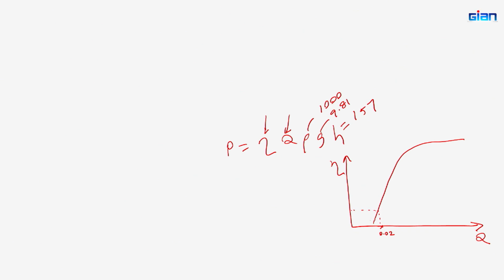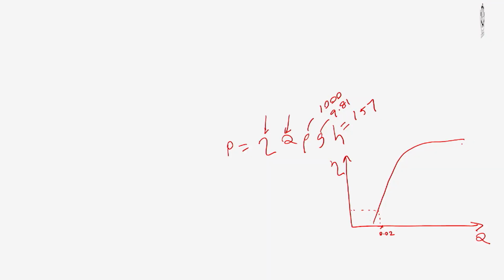One way is to fit a curve for this efficiency curve. How do we get the efficiency curve? We can get it from the turbine supplier. He will say this is the efficiency curve for my turbine. Once you know the efficiency curve, theoretically you can fit a curve on this. I am sure all the engineers are familiar with curve fitting techniques, using MATLAB or even simple hand calculations. You can fit a parabolic or some other curve suitable for this shape. Then you can just insert the flow value and calculate the efficiency. So, the efficiency will be an equation of flow. You can derive an equation for efficiency by fitting a curve here.